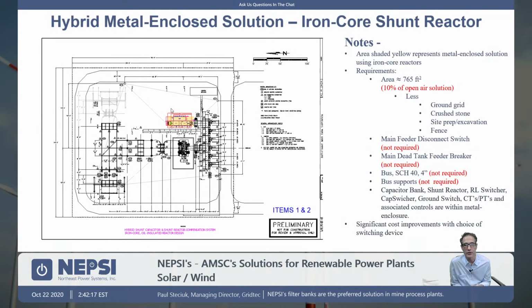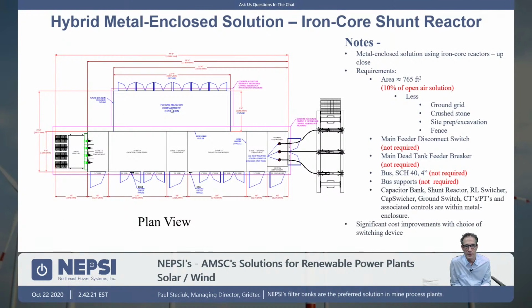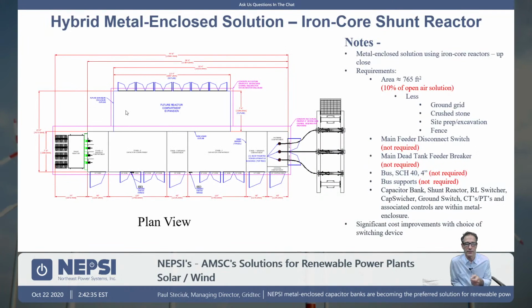And this is a filter ready cap bank with a shunt reactor on it. So kind of this is how it looks. So it's much simpler. It's a single enclosure with a shunt reactor on the end. This enclosure here is an add-on piece should in the future that cap bank need to be converted to harmonic filter.